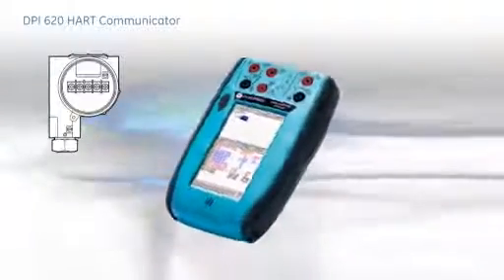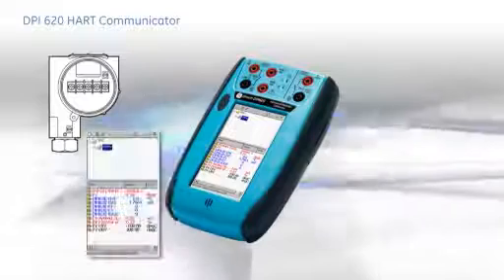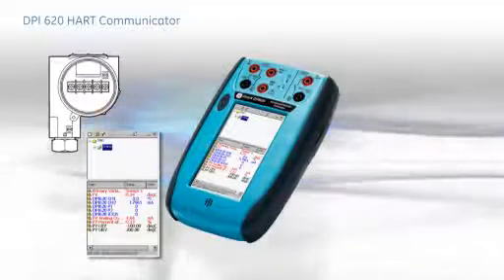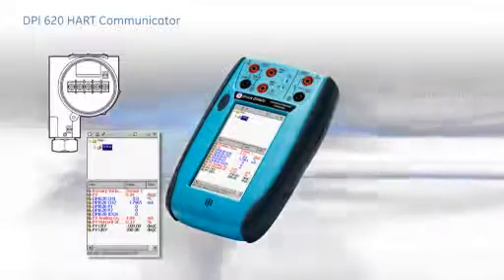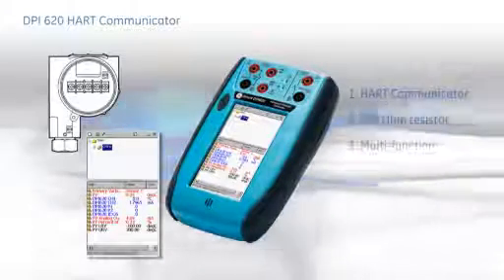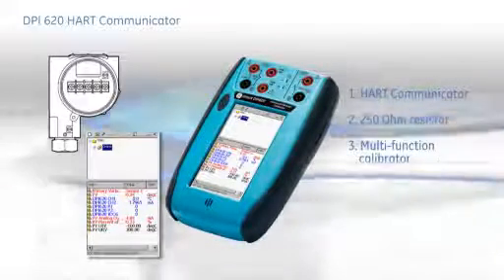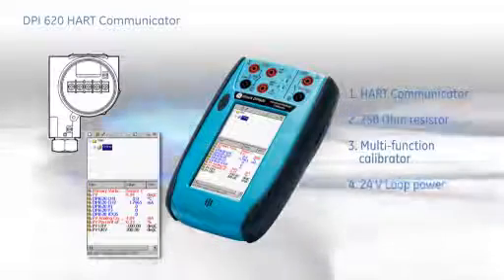Not so with the DPI-620. It's the smallest device of its type and includes milliamp measurement and all the reference parameters for electrical, frequency, temperature, and pressure. It can provide 24 volt loop power and even has a 250 ohm loop resistor built in.